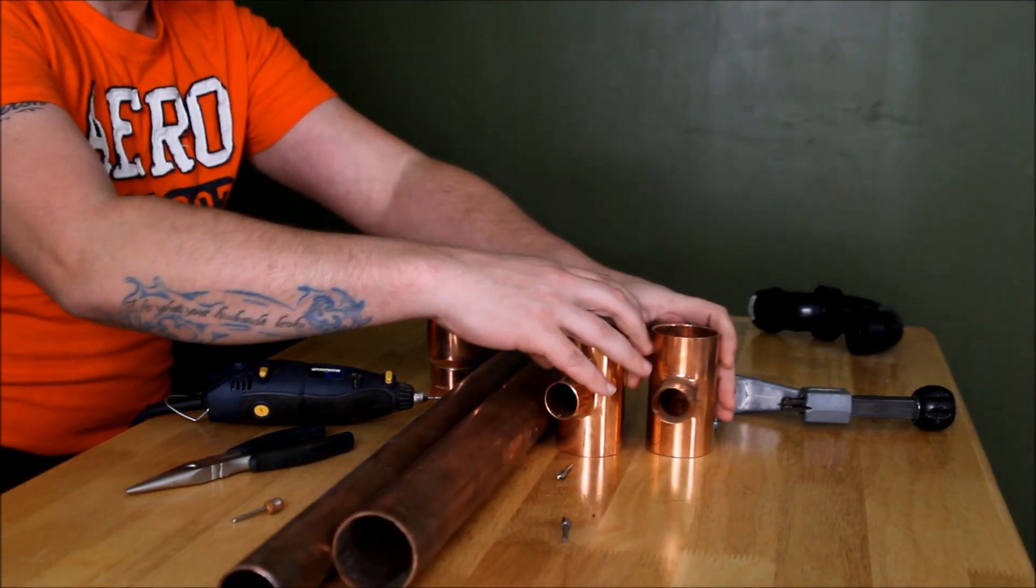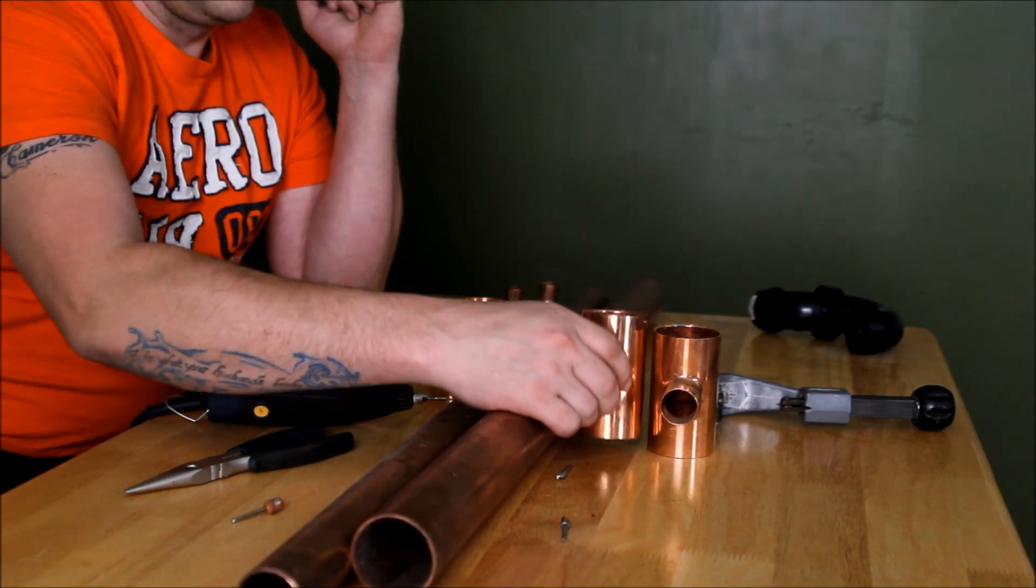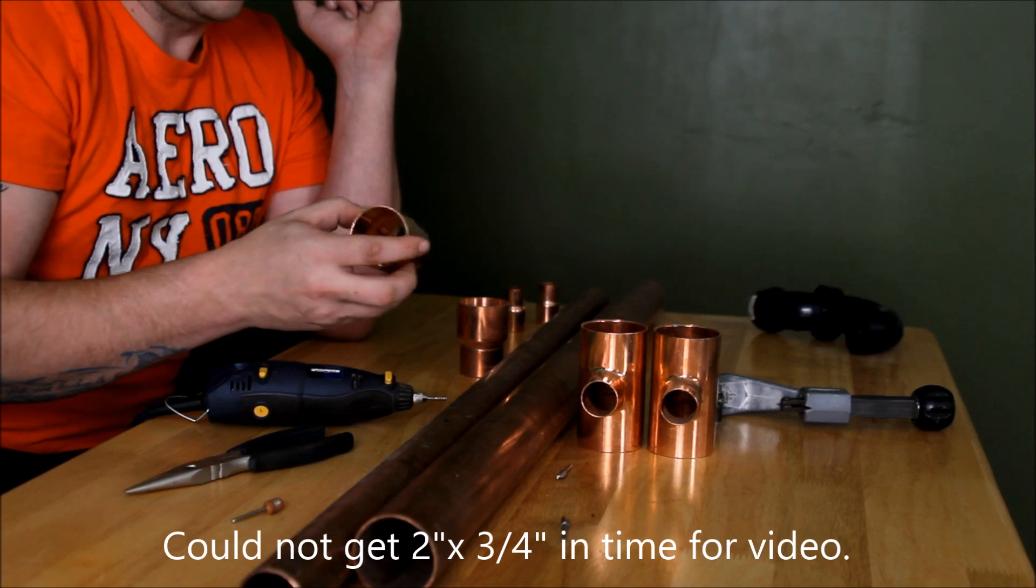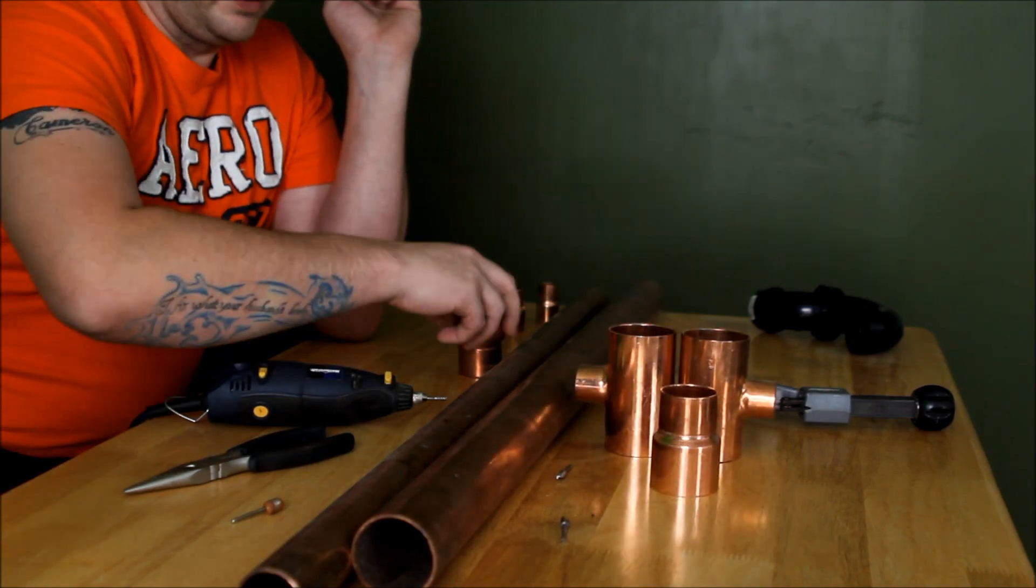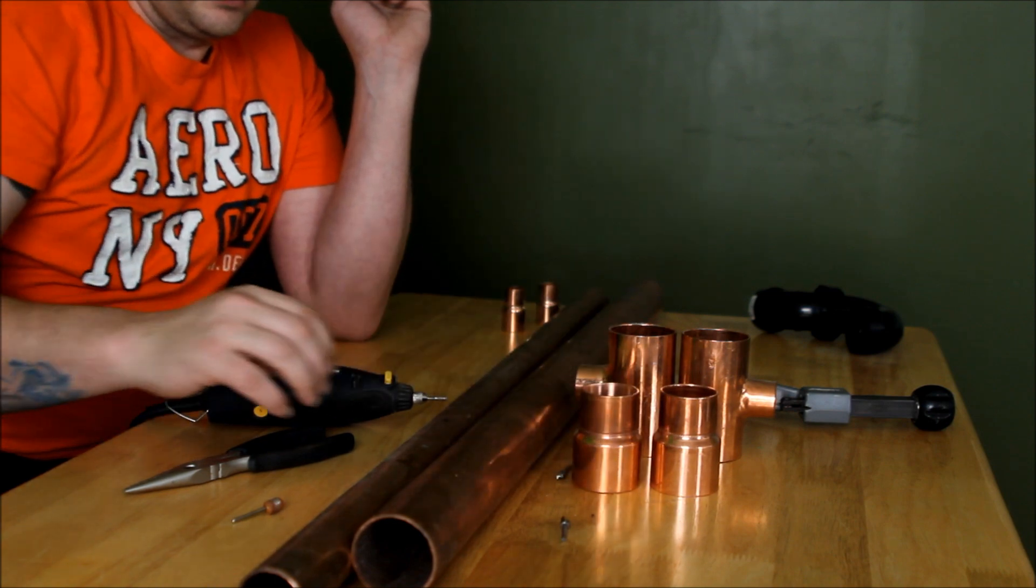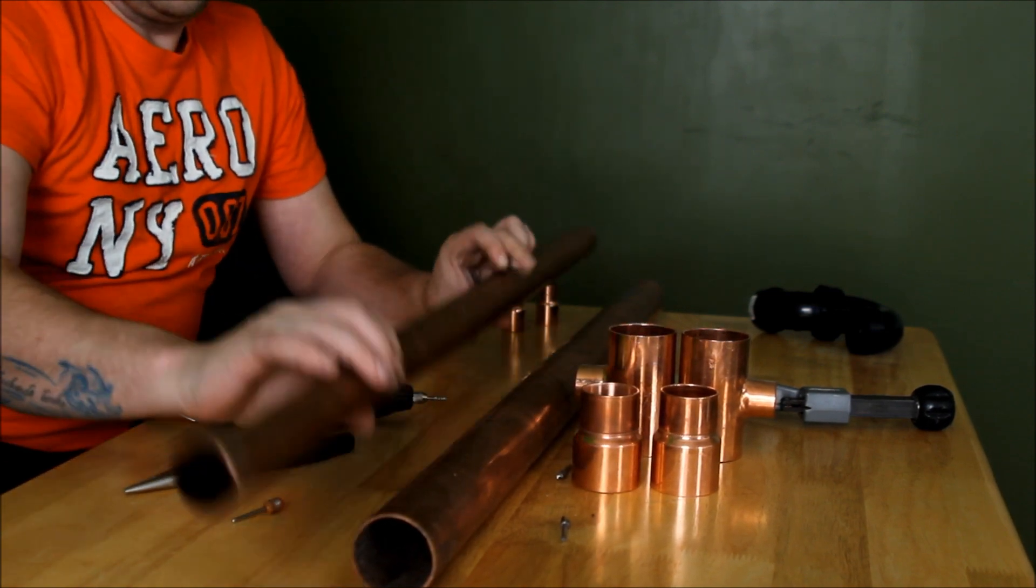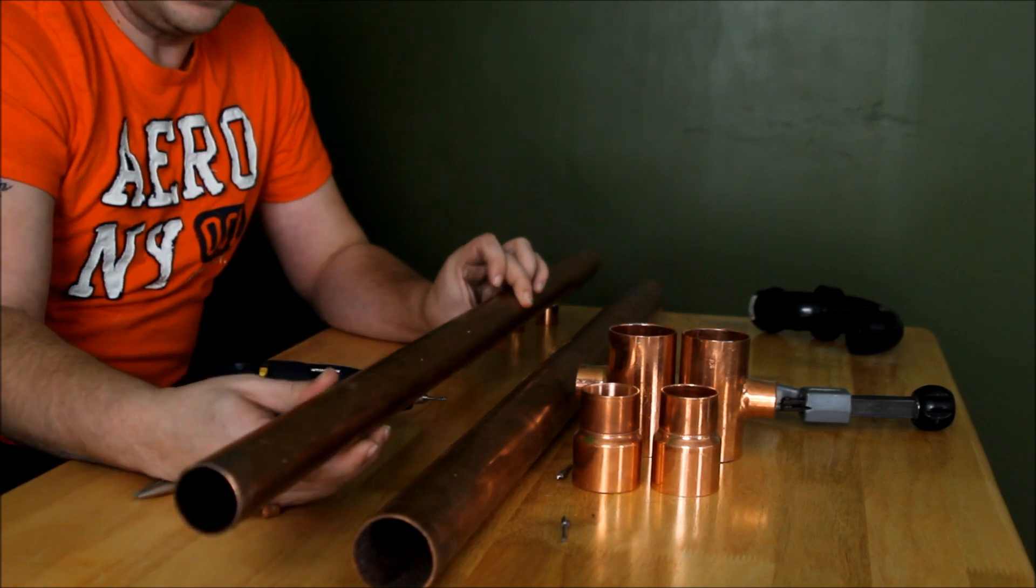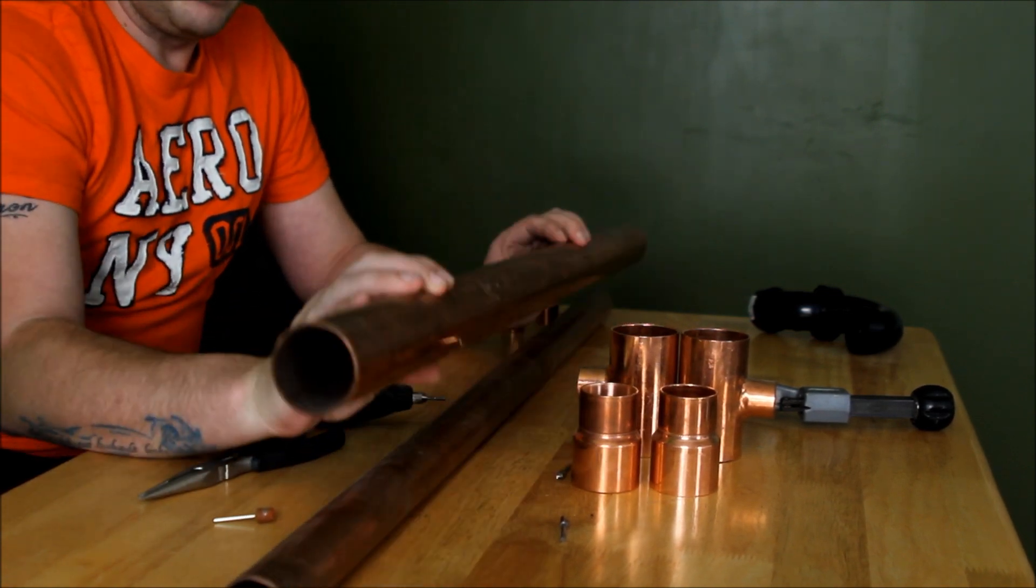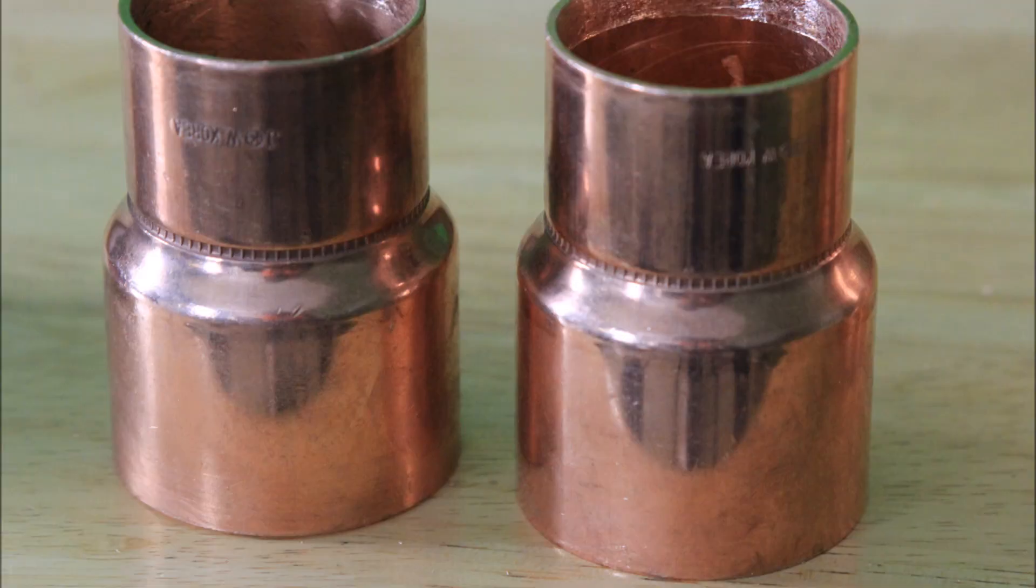What we're starting off here with is two 2-inch by 1-inch reducing tees. I've got two reducing bushings, 2-inch by inch and a half. I've got two pieces of pipe. Since we're dealing with domestic pressure, this is type M, and this is type M also. Now, see that edge stamped around the middle of the bushing? We need to remove that. We do that by using a Dremel tool.